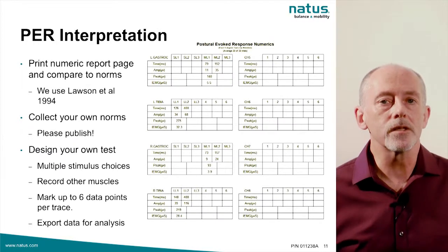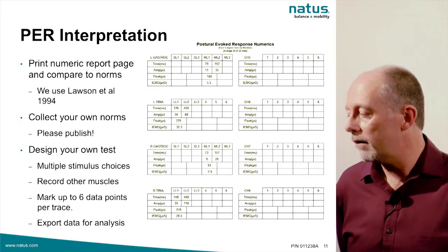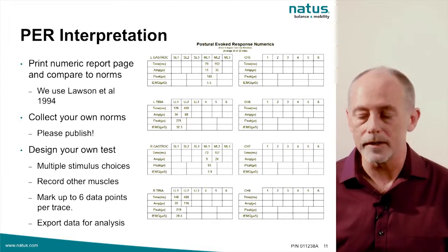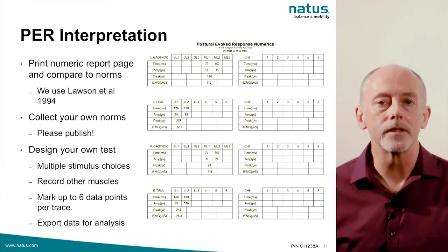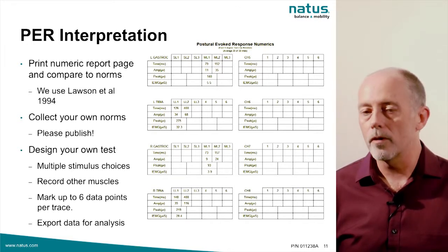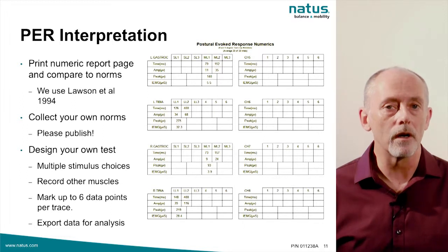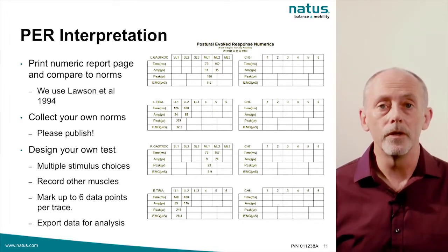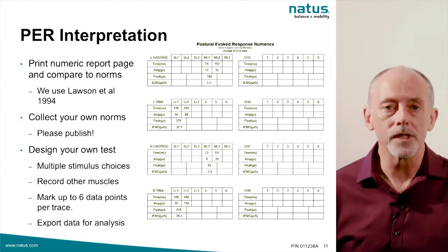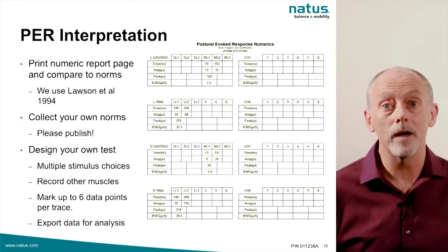The Postural Evoked Response Test is interpreted by performing the test, marking the latencies manually, and then comparing the latency and amplitude data obtained to published normative data. We use Lawson et al. 1994, published in the Journal of Vestibular Research, for our normative data. Keep in mind that when recording toes-up tilts from tibialis and gastroc, that's the standard clinical protocol — but the PER Test is very flexible. You can use any motion profile, including translation, toes-up, or toes-down tilts, and record from any muscle group. The standard test protocol is simply what we have published norms on.